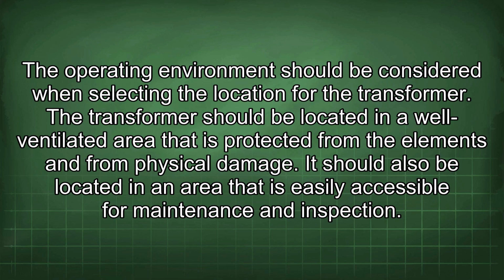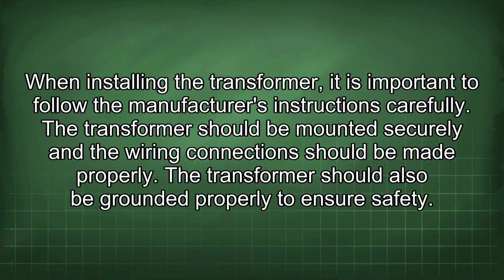The transformer should be located in a well-ventilated area that is protected from the elements and from physical damage. It should also be located in an area that is easily accessible for maintenance and inspection. When installing the transformer, it is important to follow the manufacturer's instructions carefully. The transformer should be mounted securely and the wiring connection should be made properly. The transformer should also be grounded properly to ensure safety.